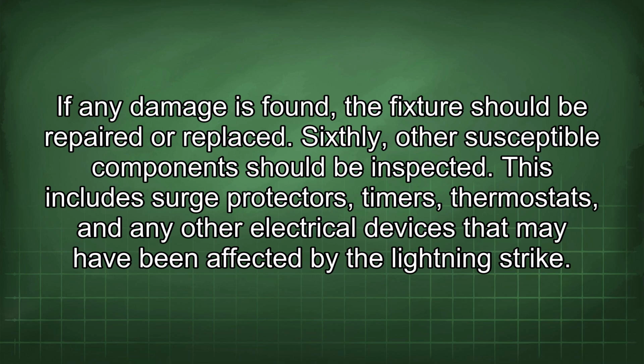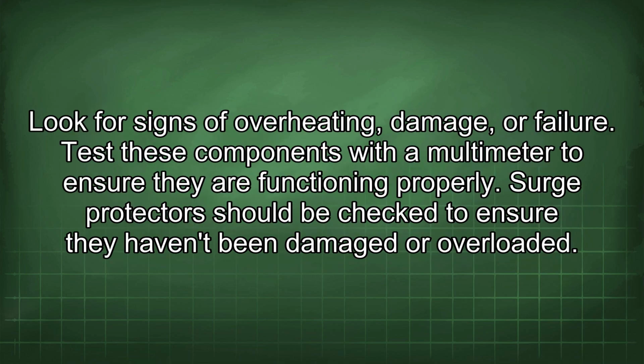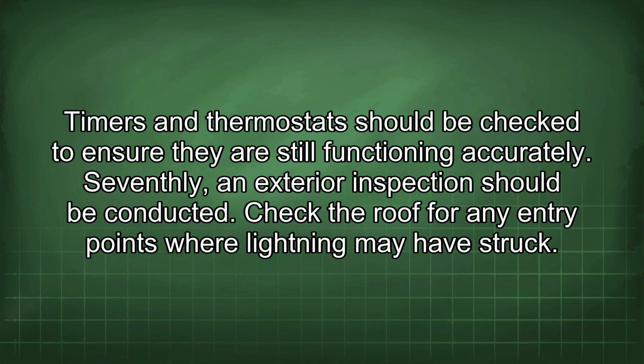Sixthly, other susceptible components should be inspected. This includes surge protectors, timers, thermostats, and any other electrical devices that may have been affected by the lightning strike. Look for signs of overheating, damage, or failure. Test these components with a multimeter to ensure they are functioning properly. Surge protectors should be checked to ensure they haven't been damaged or overloaded. Timers and thermostats should be checked to ensure they are still functioning accurately.